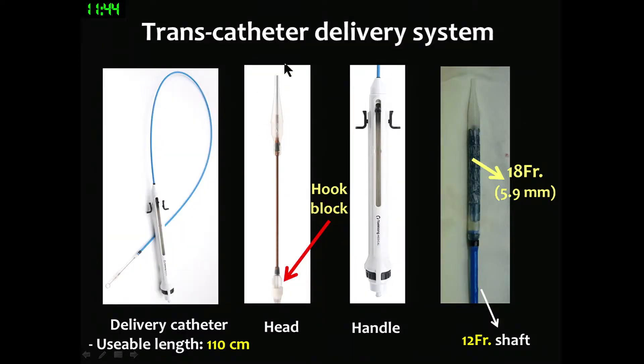This is the transcatheter delivery system. The total length is 110 cm. At the header portion, we made a hook block, which we modified several times. The hook block prevents the valve from jumping during deployment, and it also serves as an anchoring point to recapture the valve back into the delivery catheter if needed. By rolling the knob, we can deploy half of the valve, and by pulling the lever, we can deploy the valve fully.